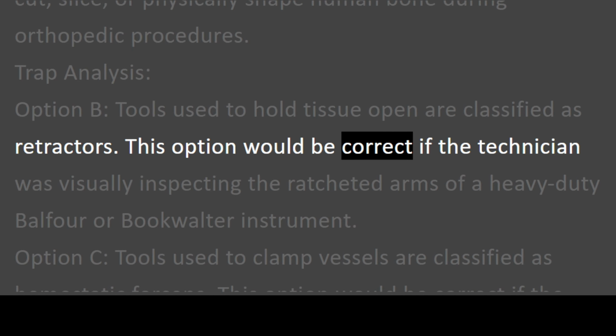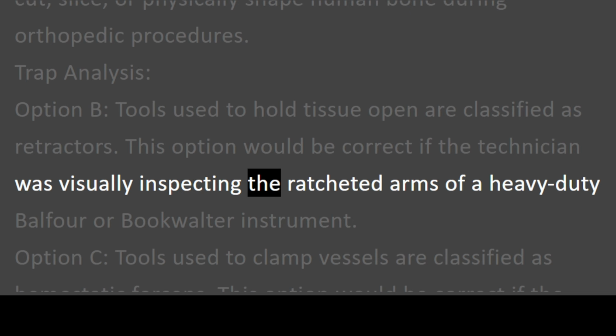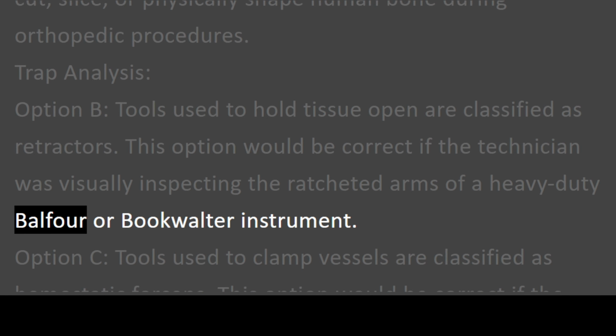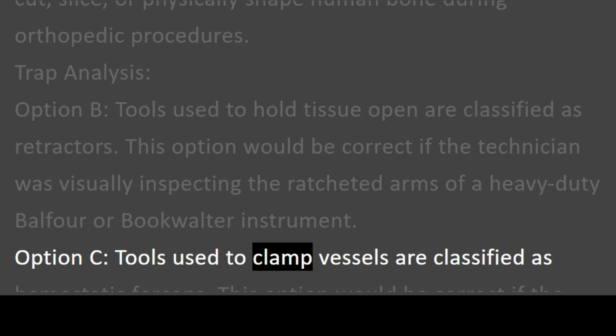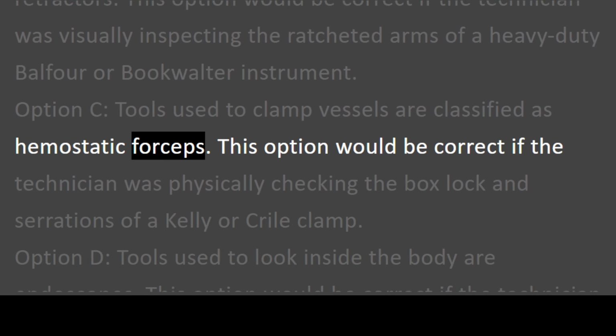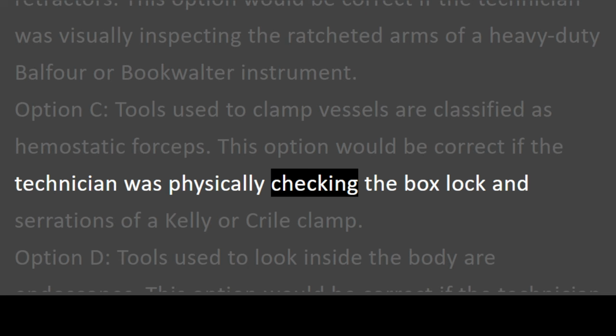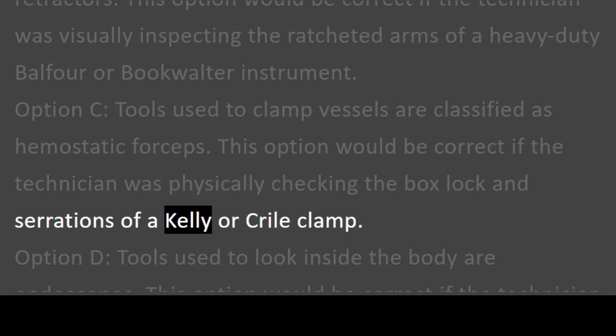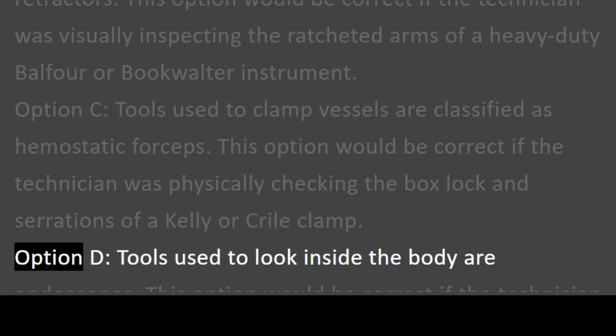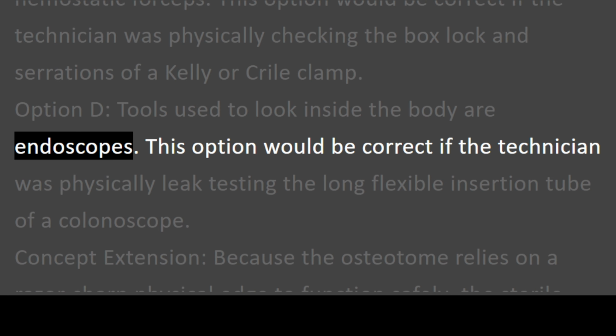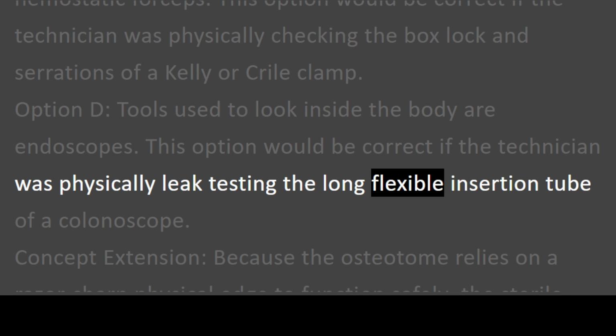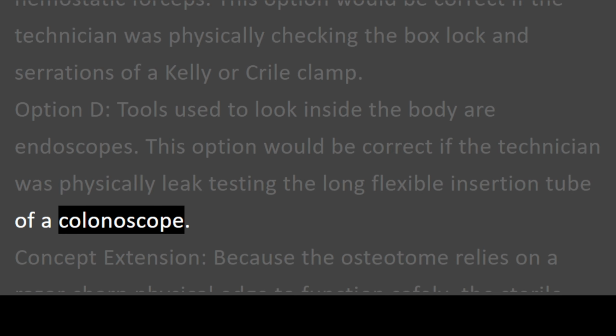This option would be correct if the technician was visually inspecting the ratcheted arms of a heavy-duty Balfour or Bookwalter instrument. Option C. Tools used to clamp vessels are classified as hemostatic forceps. This option would be correct if the technician was physically checking the box lock and serrations of a Kelly or Crile clamp. Option D. Tools used to look inside the body are endoscopes. This option would be correct if the technician was physically leak testing the long flexible insertion tube of a colonoscope.